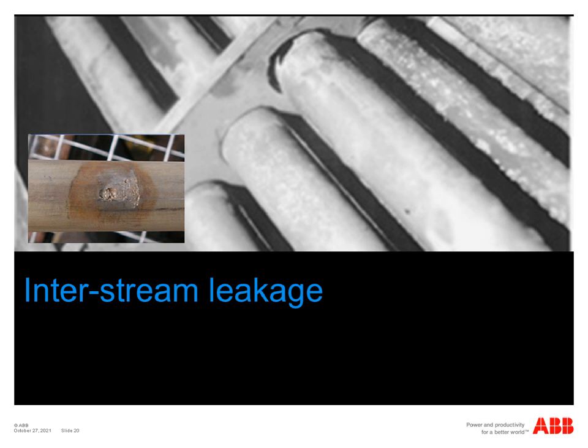And then you've got this huge differential pressure, which makes the tube rupture case very serious. This is difficult to design out, because if you wanted to make the system inherently safe, you would make the LP side good for the HP side design pressure, but because you've got this huge differential, making the LP side good for 200 bar in the example I just mentioned would be a very expensive, very costly activity to do. And it wouldn't necessarily be just the exchanger. You would need to increase the design pressure of the LP side. You'd perhaps have to make a large part of the cooling system suitable for handling that larger pressure. So that's obviously going to have a very big impact on the cost of your equipment, and it may be uneconomical to do that.